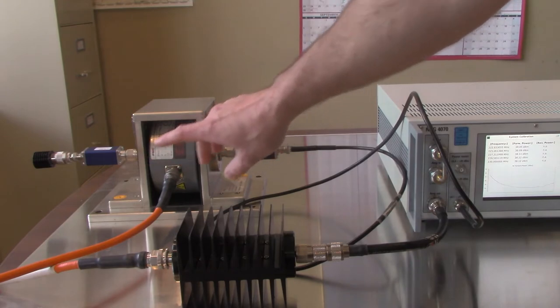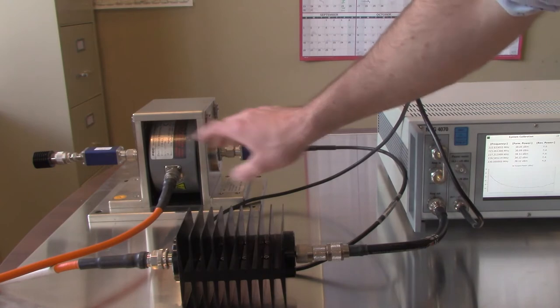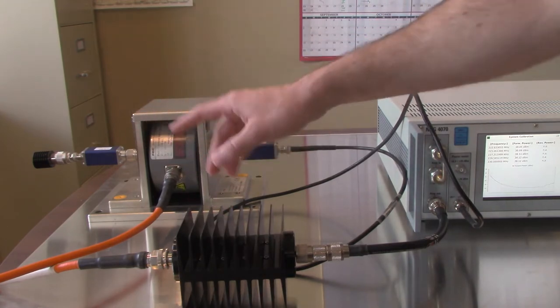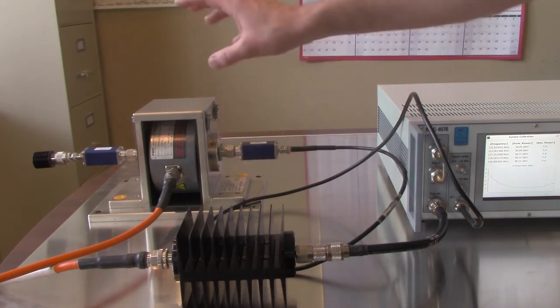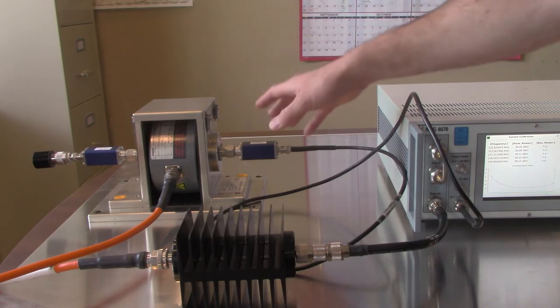Alright, working our way left here, you will see our 50 to 150 adapter followed by our termination load. These 50 to 150 adapters are used for IEC 61000-4-6 during the calibration setup which we're doing today. However, this isn't always the case with other bulk current injection requirements.